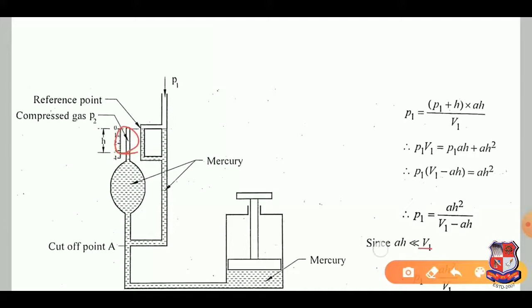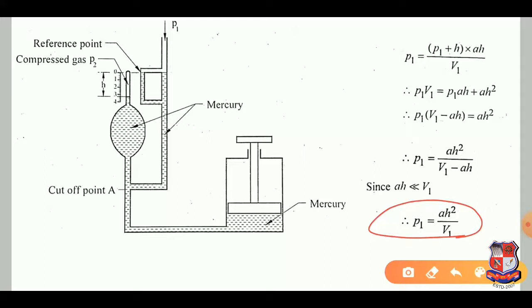The McLeod gauge is very accurate for low pressure measurement and often serves as a standard for calibrating other low pressure gauges. The working range of the McLeod pressure gauge is from 0.00001 to 1 torr.